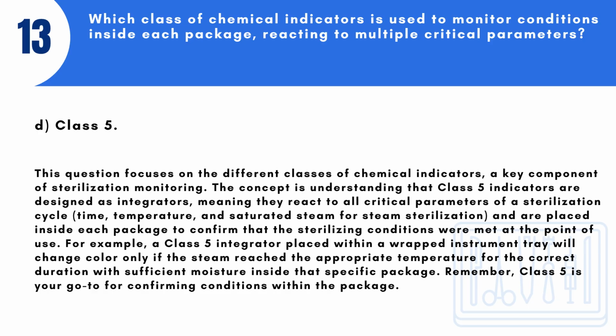For example, a Class 5 integrator placed within a wrapped instrument tray will change color only if the steam reached the appropriate temperature for the correct duration with sufficient moisture inside that specific package. Remember, Class 5 is your go-to for confirming conditions within the package.